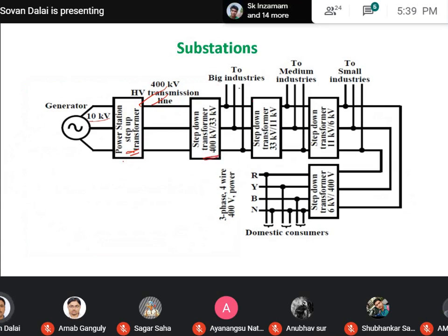Some of the big industries require that voltage level, and again that 33 kV is stepped down by using another transformer. That is called the step down substation, the sub transmission voltage level stepped down for the distribution voltage level in that way. And ultimately, as a domestic consumer, we are getting the power at a voltage level of around 230 volt. So these are the steps for transmitting the generated power to the domestic consumers.